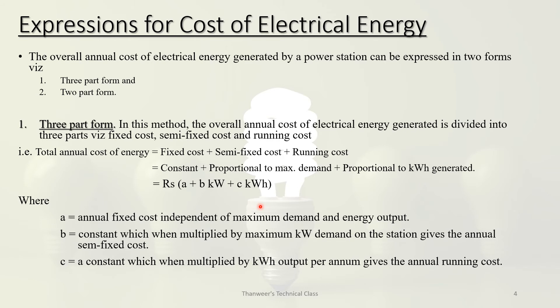kW is active power — the maximum active power output is measured in kW, and energy in kWh. In the formula, 'A' is the annual fixed cost independent of maximum demand and energy output. 'B' is a constant which when multiplied by maximum kW demand gives the annual semi-fixed cost. 'C' is a constant which when multiplied by kWh output gives the annual running cost.